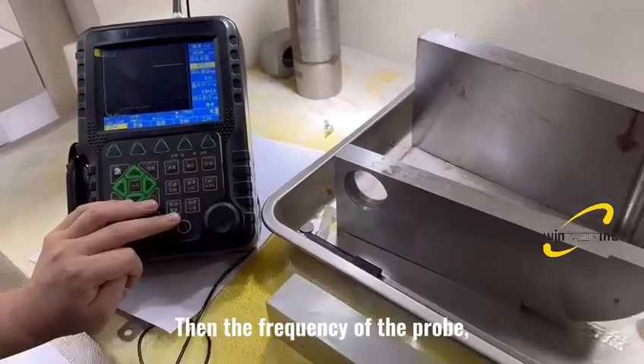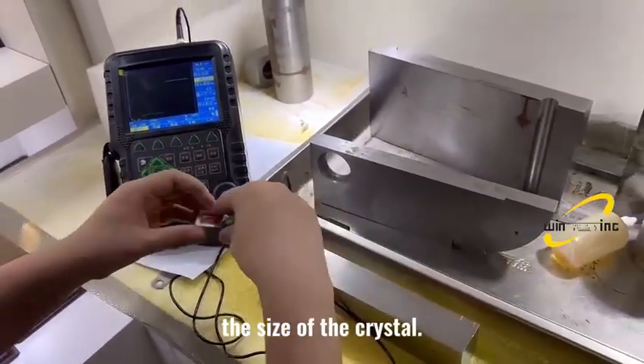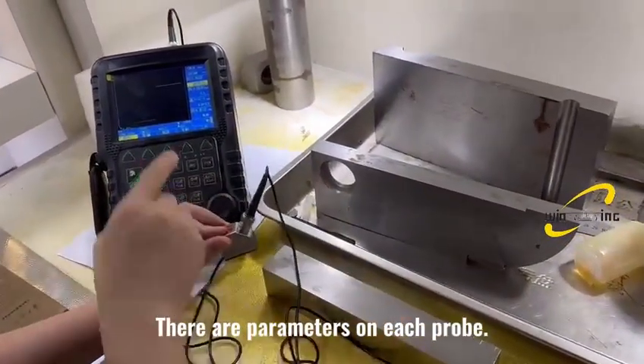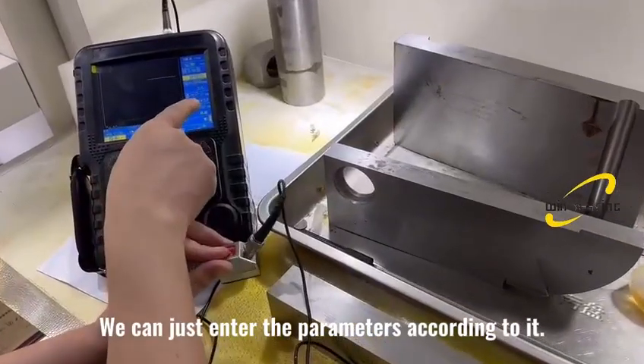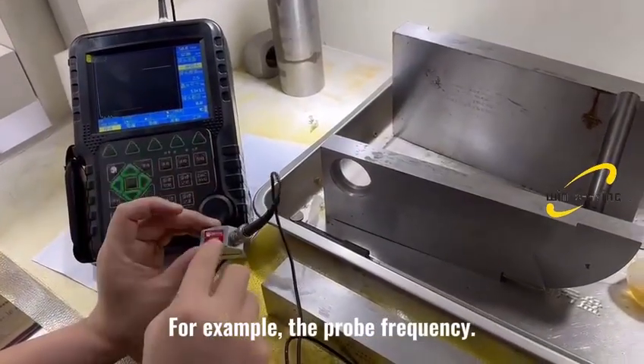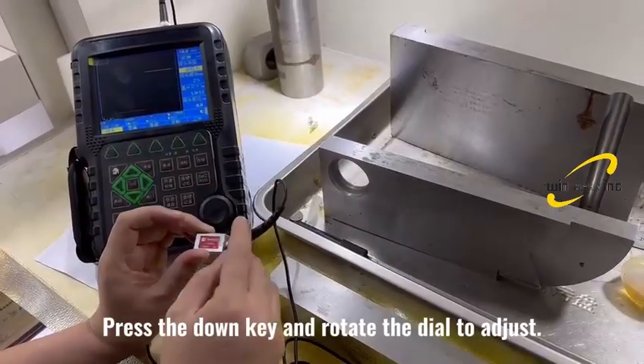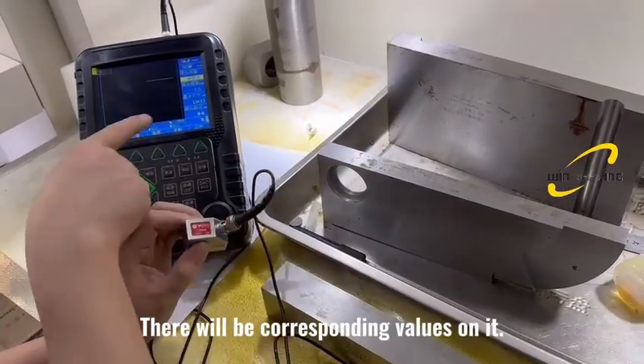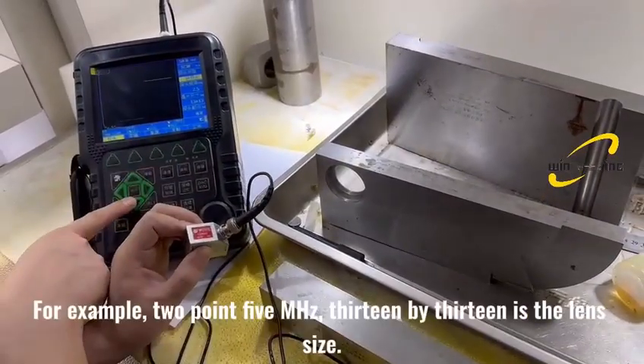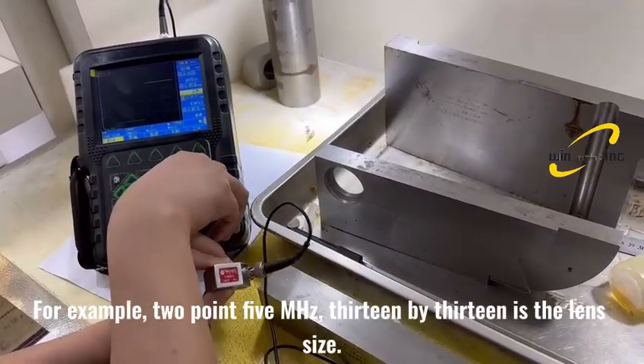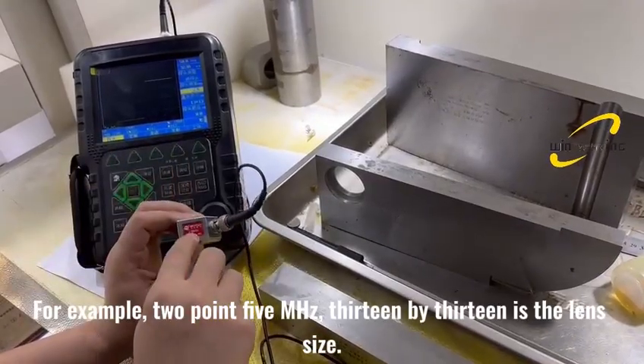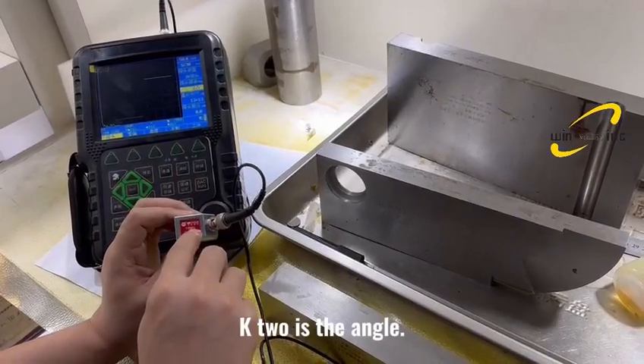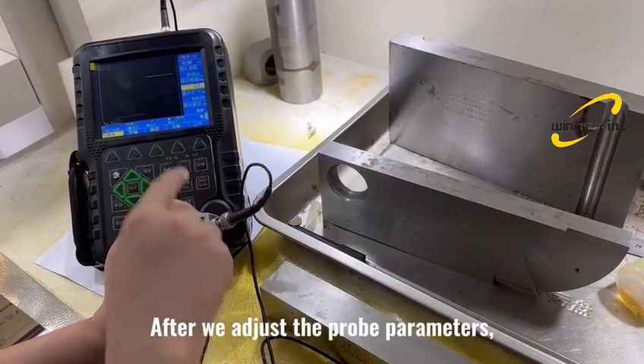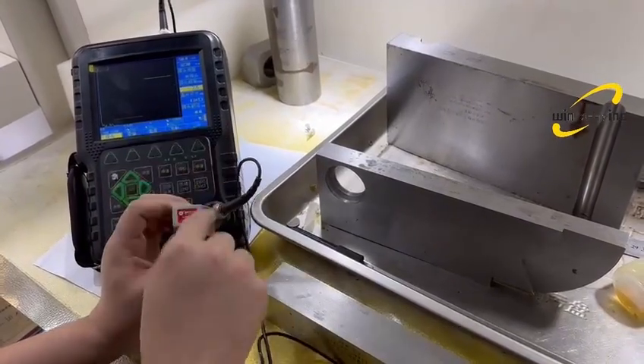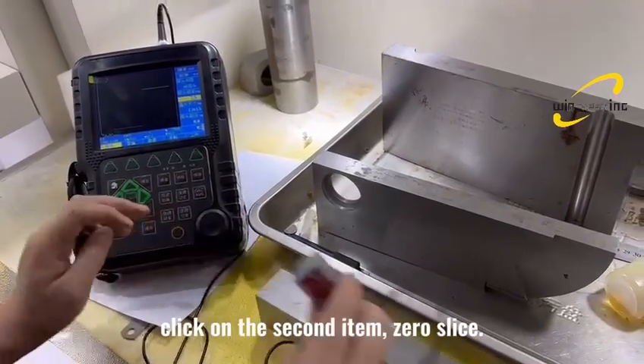Then the frequency of the probe, the size of the crystal. There are parameters on each probe. We can just enter the parameters according to it. For example, the probe frequency. Press the down key and rotate the dial to adjust. There will be corresponding values on it. For example, 2.5 MHz, 13 by 13 is the lens size. K2 is the angle. After we adjust the probe parameters, click on the second item, zero offset.